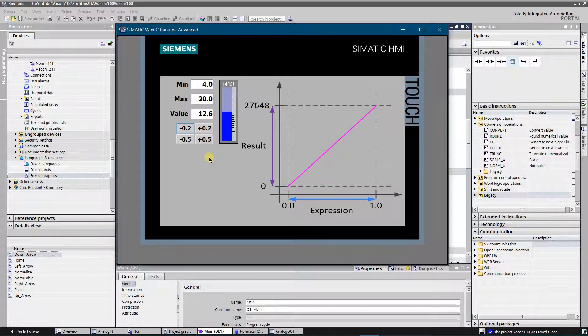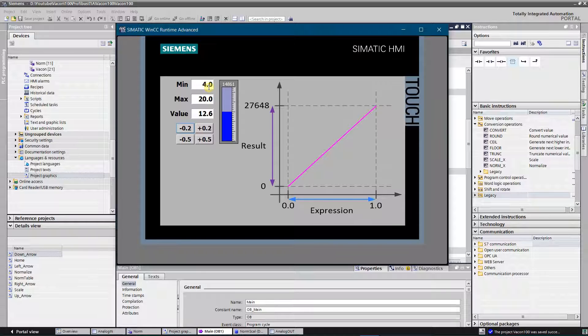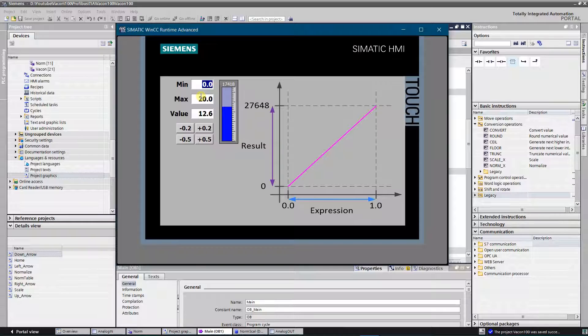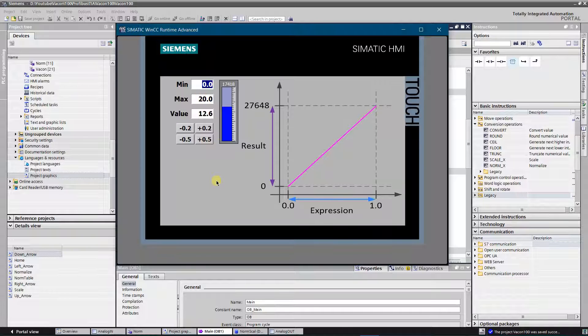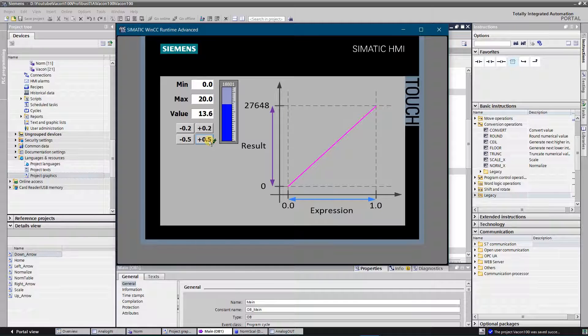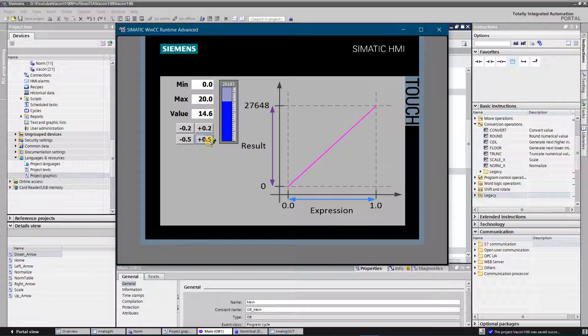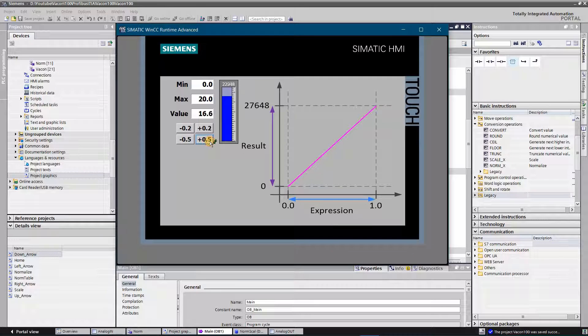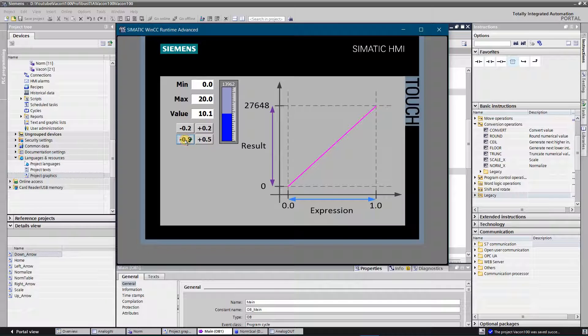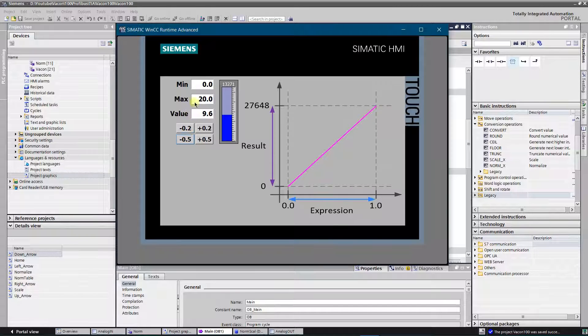Let's try to change the limits to something like 0 to 20. The value of the analog output has changed instantly. And again, analog output values are within 0 to 27,648, but now low limit is 0, and high limit is 20.